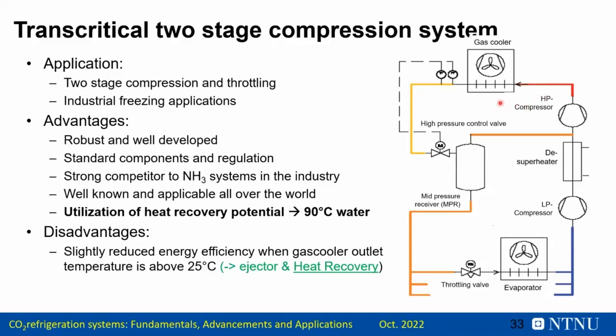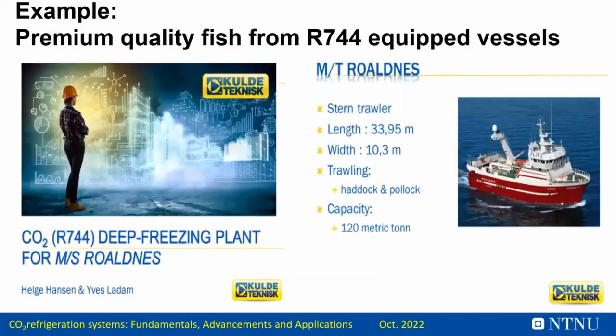This system might have a reduced energy efficiency when the gas cooler outlet temperature becomes higher than 25. That's why it's so important to look into heat recovery and find the customer who needs both very low temperature but also process water to clean the equipment and so on, because that's the winner when you can sell a system like this. An example of such an installation on a fishing vessel I will show you here.